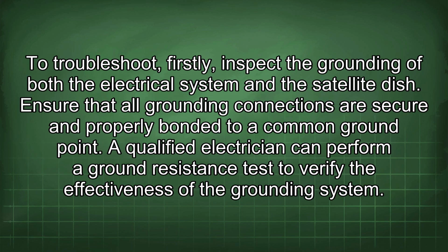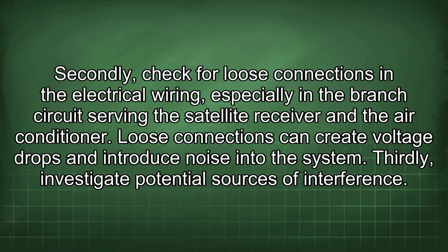To troubleshoot, firstly, inspect the grounding of both the electrical system and the satellite dish. Ensure that all grounding connections are secure and properly bonded to a common ground point. A qualified electrician can perform a ground resistance test to verify the effectiveness of the grounding system. Secondly, check for loose connections in the electrical wiring, especially in the branch circuit serving the satellite receiver and the air conditioner. Loose connections can create voltage drops and introduce noise into the system.